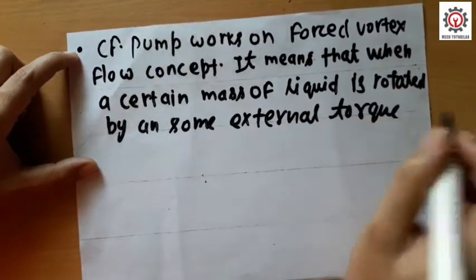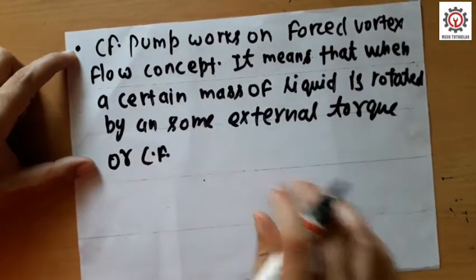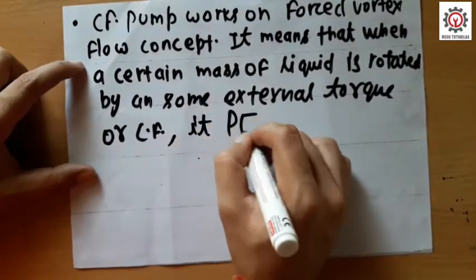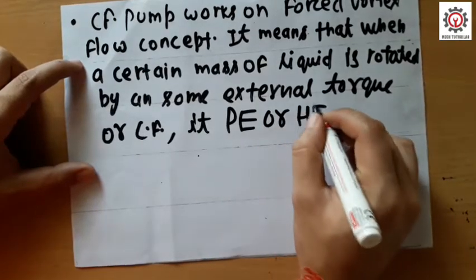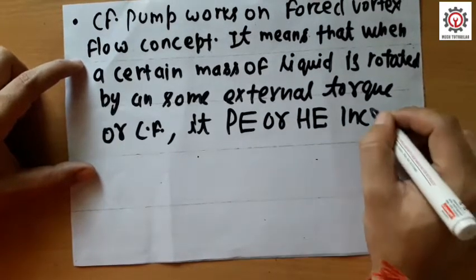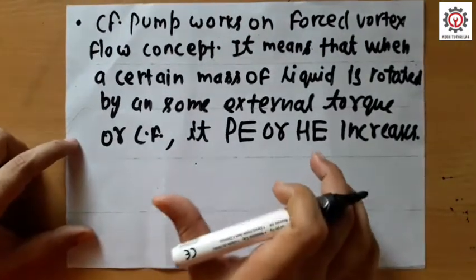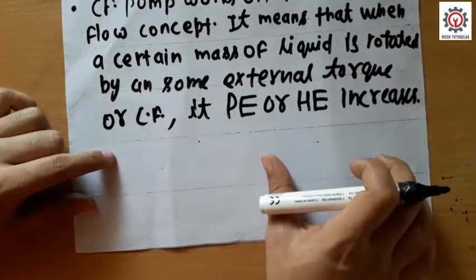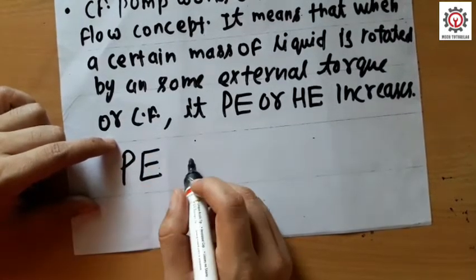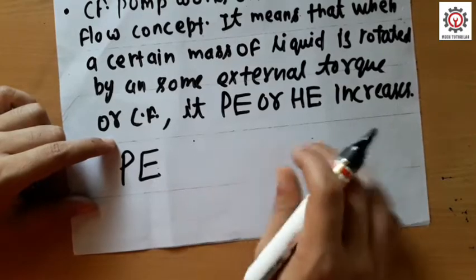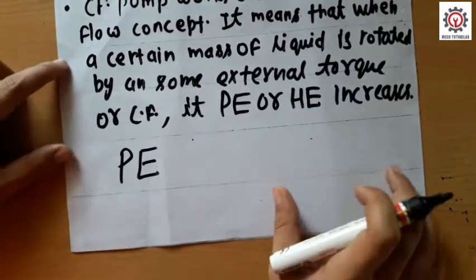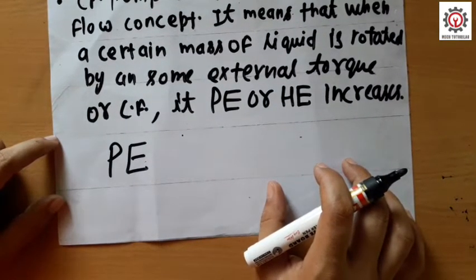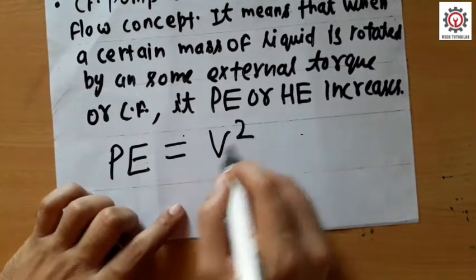Forced vortex flow means that when a certain mass of liquid is rotated by an external torque or centrifugal force, its pressure energy or hydraulic energy increases. This is the core concept of the centrifugal pump. The increase in pressure energy or hydraulic energy is proportional to the square of the tangential velocity, given by V²/2g.